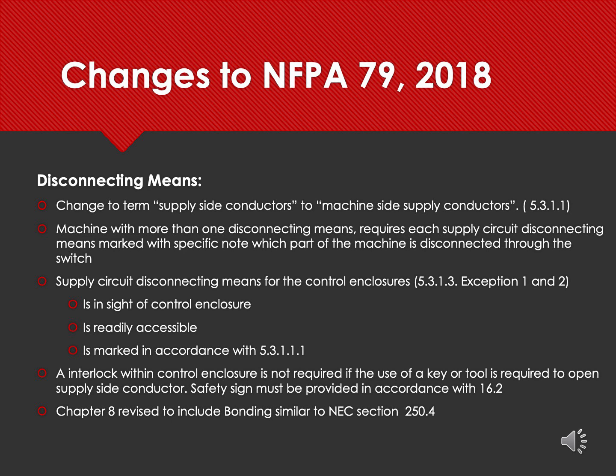Okay. Also make sure if the machine's main disconnecting means supplies more than one disconnecting means, it must be clearly marked machine's main disconnecting means. So make sure if you have multiple disconnecting means or switches within the same machinery, you need to mark whichever is the main disconnecting means. Okay. And last but not least, as John mentioned earlier, arc flash and shock hazard concerns make it more desirable to locate the supply side disconnecting means in a separate enclosure to ensure there is no power while performing the maintenance activities around the control panel. So just keep this power compartment separate from all the control gear inside your panel.